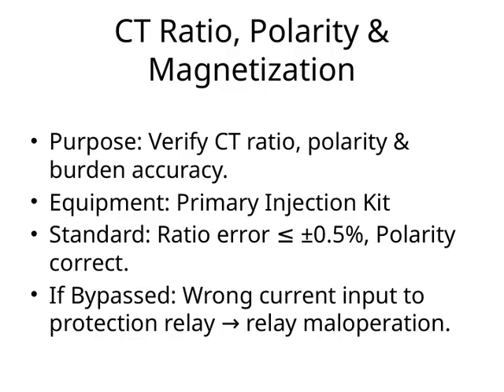Let's talk about CT ratio, polarity, and magnetization. The main purpose here is to verify that the CT ratio, polarity, and burden are all accurate. This is essential because if any of these are off, it can affect the overall protection system performance. To do this, we use a primary injection kit, which allows us to simulate the current flowing through the CTs safely and accurately. We have a standard to follow.